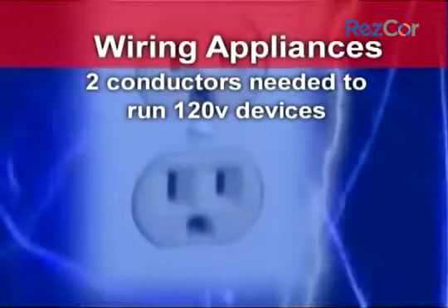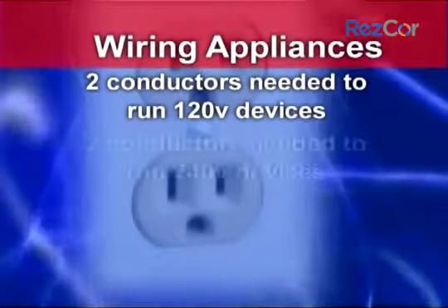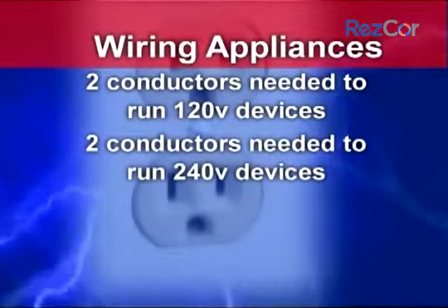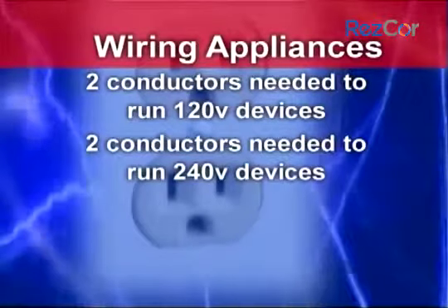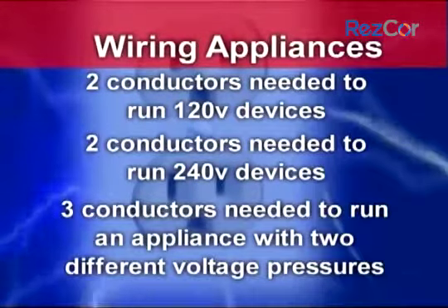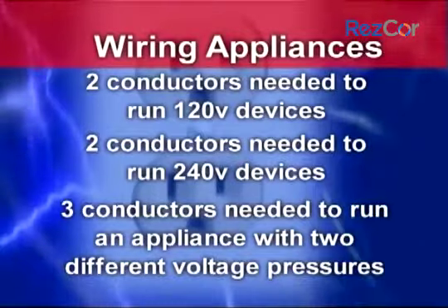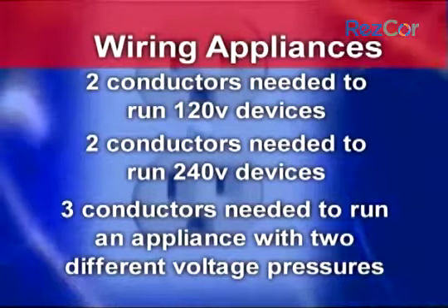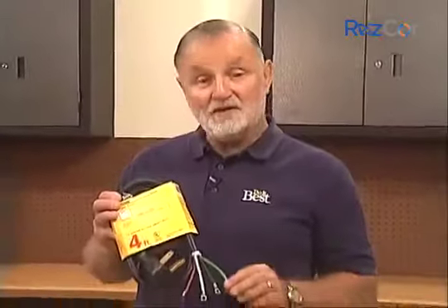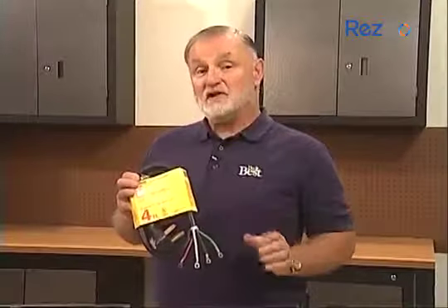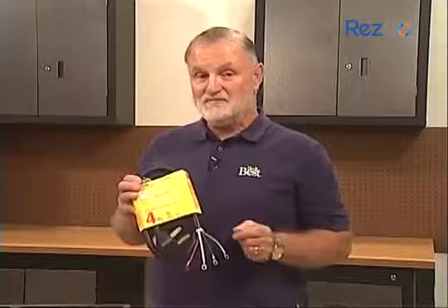Try to remember it this way. You need 2 conductors to run 120 volt devices, and you need 2 conductors to run 240 volt devices. But it takes 3 conductors to operate any appliance that has 2 different voltage pressures in it. Newer range and dryer cables also have a 4th wire that's green. This is a grounding wire, which we'll talk about in a minute.